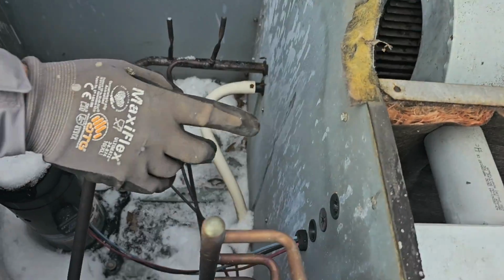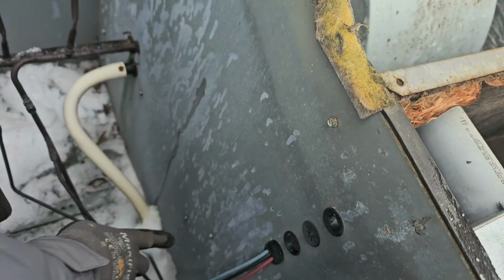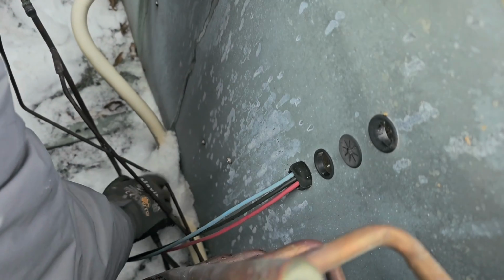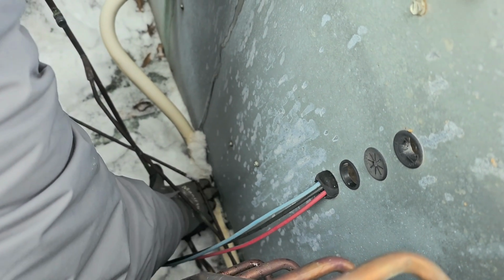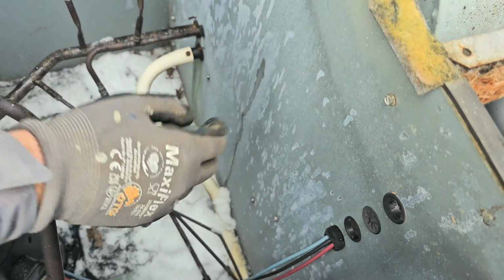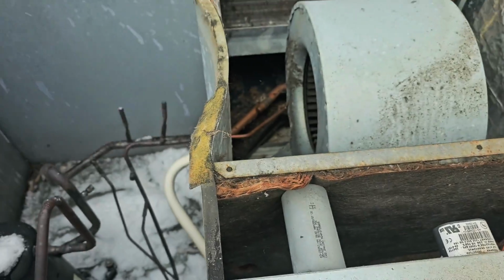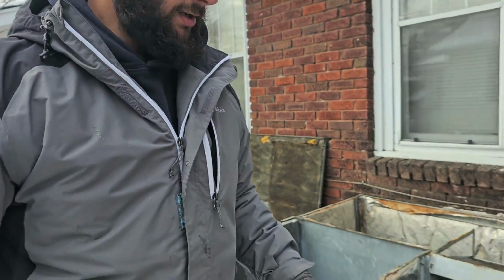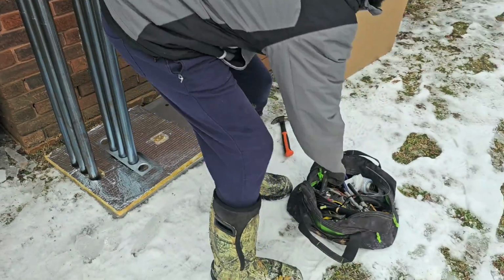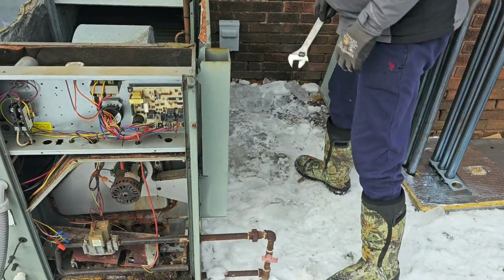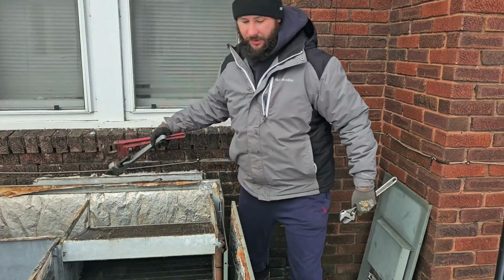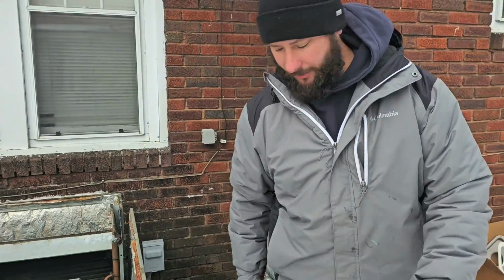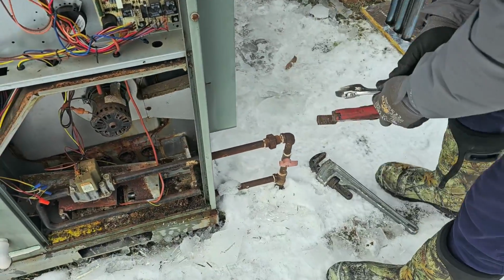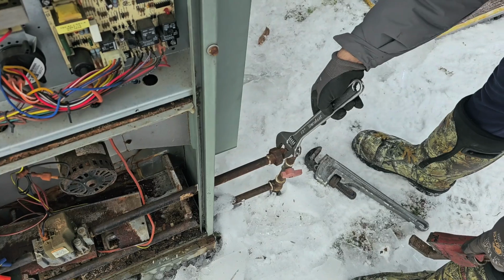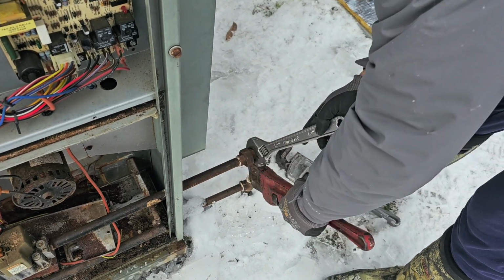There's some screws in here that are connected to the heat exchanger. One is here, one is here, and one is down here, and it's behind that PVC pipe. So we'll have to take the pipe loose here to get to that last screw that holds this side of the heat exchanger in. Now, what we're going to do is loosen the union. You can use a couple pipe wrenches. If you can't get your pipe wrench in there on one side because it's too close to the elbow, use your crescent wrench.